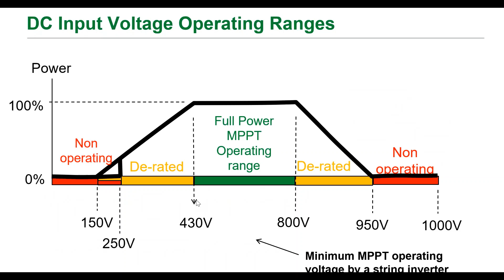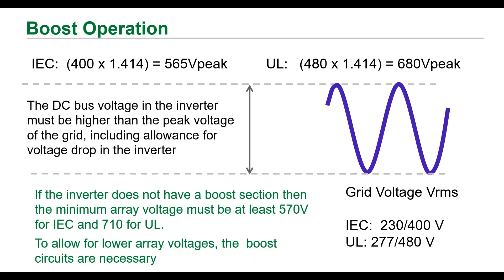Whereas in North America, it's a 480 volt system, so for a 480 volt system it should be 680 volt peak - your DC link should be 680 volt. To maintain this voltage you need a boost converter, because here 430 volt is coming in and needs to be pumped up to 565. So you need a boost converter, which requires an inductor and capacitor to store energy, and by using proper switching mechanism you can boost the voltage so that your DC link voltage is maintained.